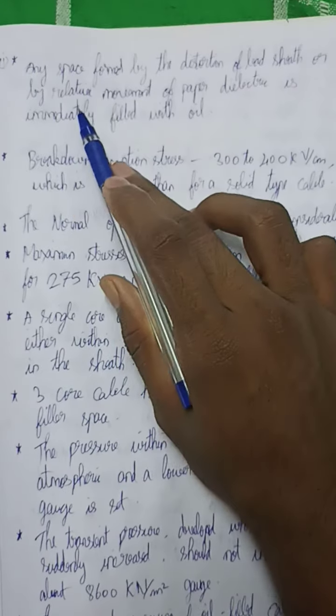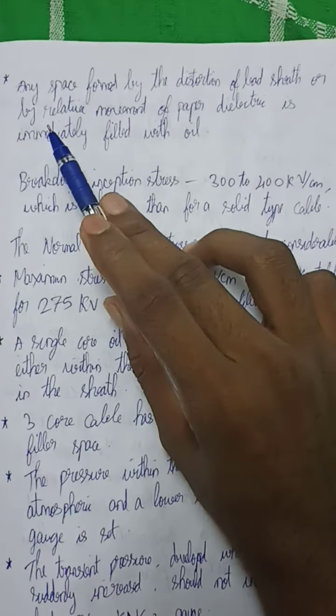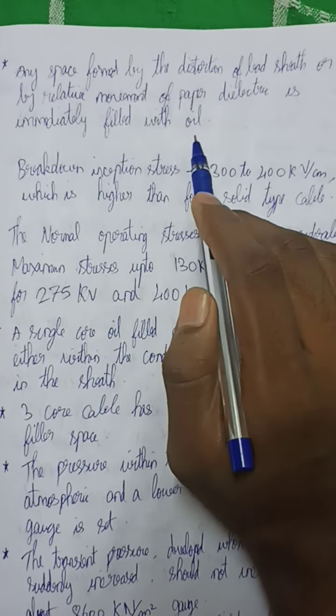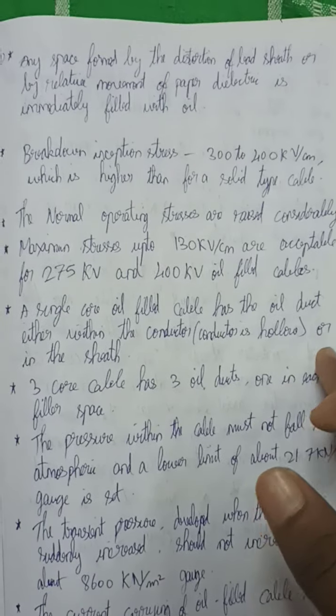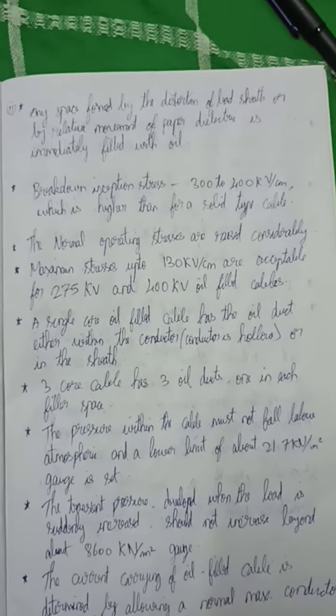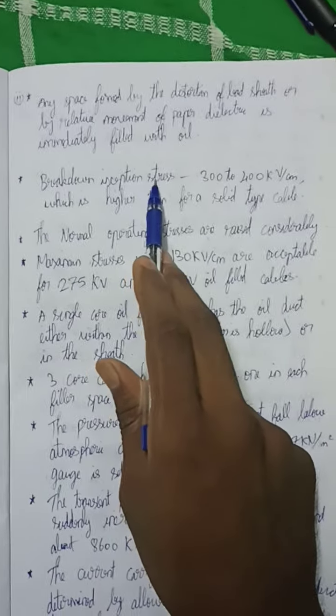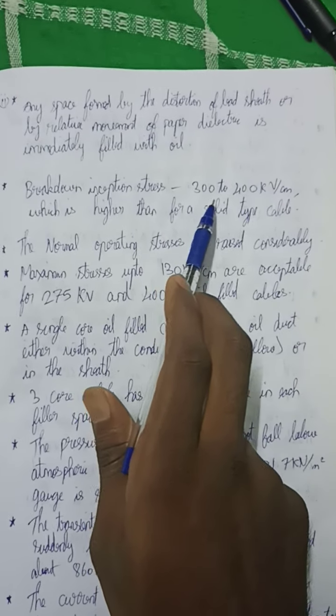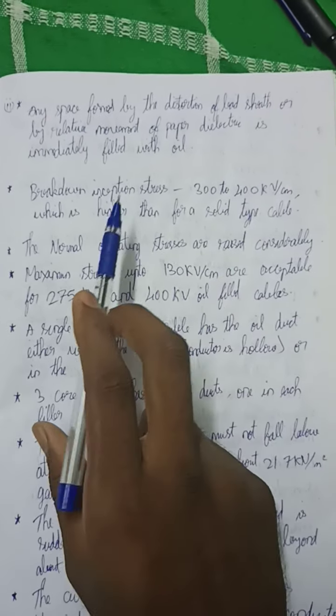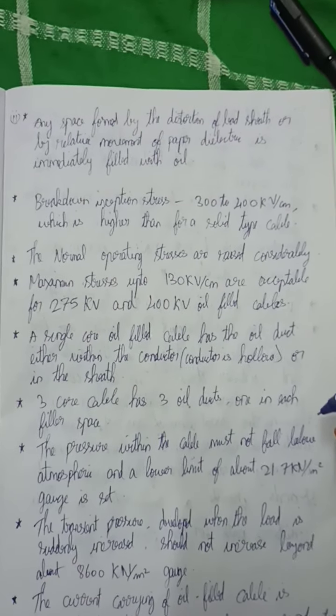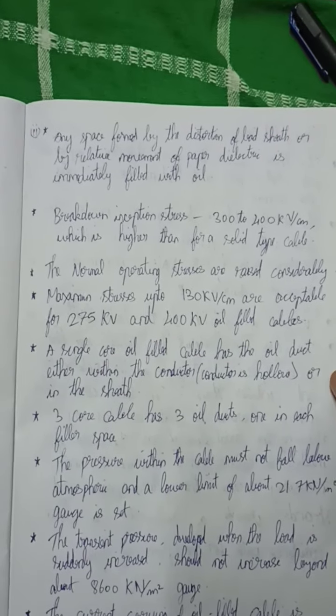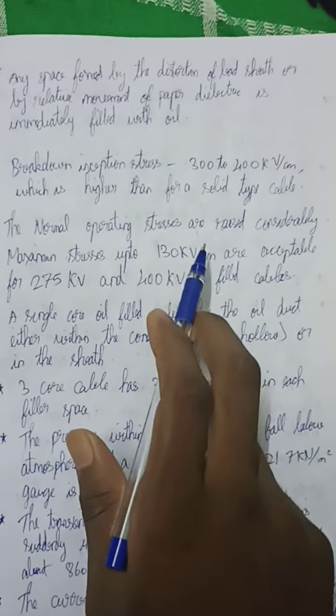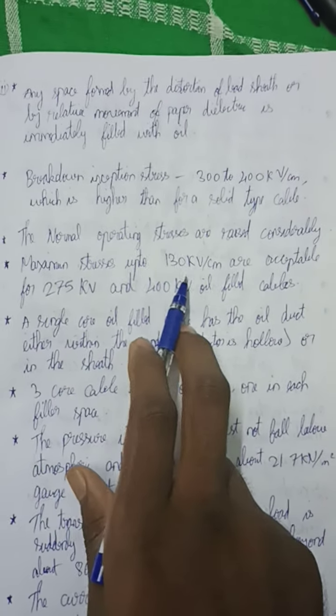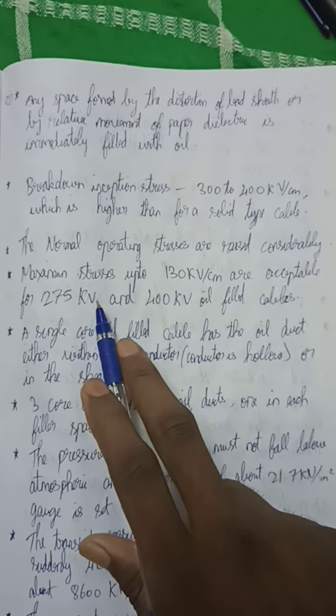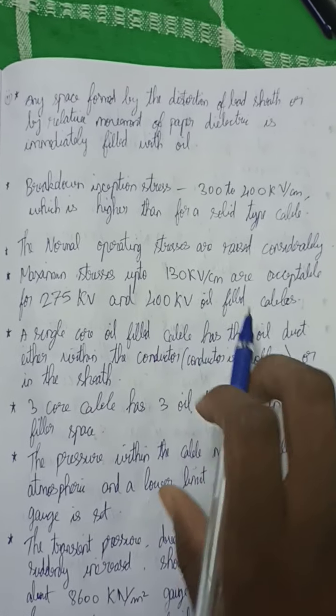And the next advantage is any space formed by the distortion of the lead sheath or by relative movement of paper dielectric is immediately filled with oil. Those are the main advantages of oil filled cables. The breakdown inception stress of oil filled cables is 300 to 400 kV/cm, which is much higher than for solid type cables. Normal operating stresses are raised considerably. Maximum stresses up to 130 kV/cm are acceptable for 275 kV and 400 kV oil filled cables.